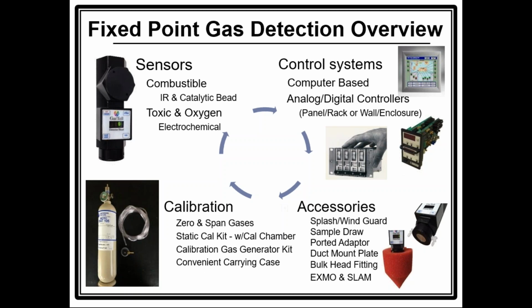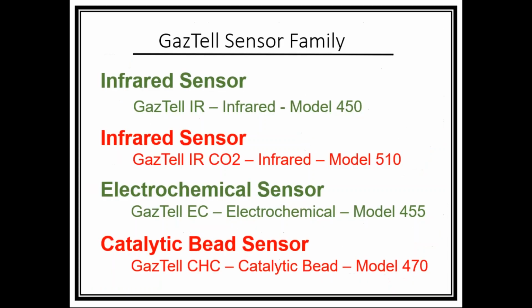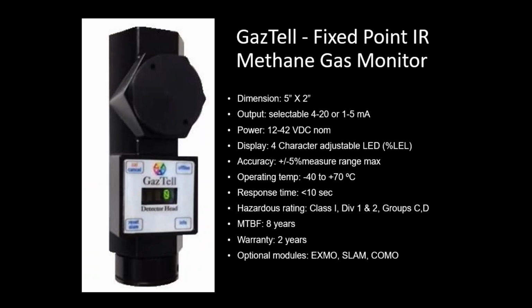The accessories that we have, we're going to get into a little bit later in the webinar, and those allow you to customize the system to the requirements of your customer. If he's monitoring in an oven, if he's monitoring in a duct, we have accessories that allow you to mount the sensor in the duct. We have accessories that allow you to take a sample out of the oven and bring it to the sensor. If it's a heated sample, we can cool it using a little heat exchanger that we can build, or you can do that yourself, or the customer can do that.